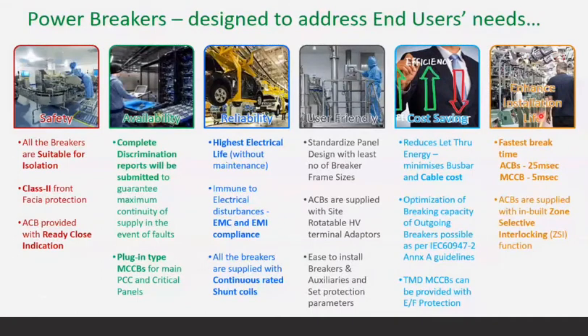We have seen at the start of the slide that in the total cost of installation, almost 10% is the electrical package, and out of that 10%, only 2% is the protection devices or the switchgear cost. So how can I enhance the installation life? These are a few data points again. Our ACBs and MCCBs have the world's fastest break time. If it is an ACB, it is 25 milliseconds, and if it is an MCCB, it is 5 milliseconds.